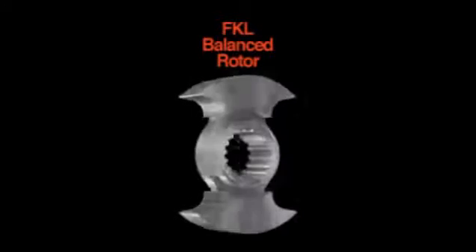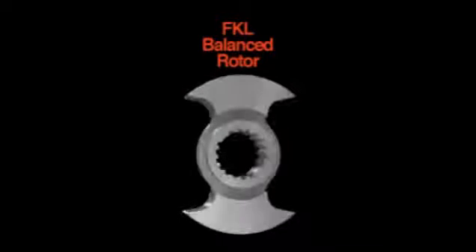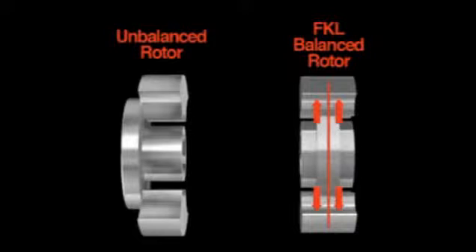Deflection is where force displaces or bends a structure from its normal position. With a Fristam FKL rotor, the support hub is centered so that force acts through the center of the rotor to keep the lobes from deflecting.